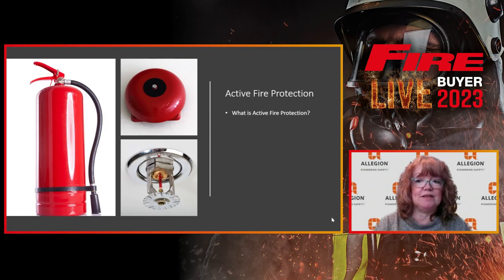Sprinklers are quite sophisticated and are designed to be heat sensitive so that the sprinkler only activates when temperatures rise to fire-induced temperatures. Fire extinguishers are a handheld active fire protection device. There are 5 classes of extinguishers, classes A to E, A being used on ordinary combustibles like wood, rubber, paper, as well as some plastic materials. Some extinguishers also have multiple classes of use.